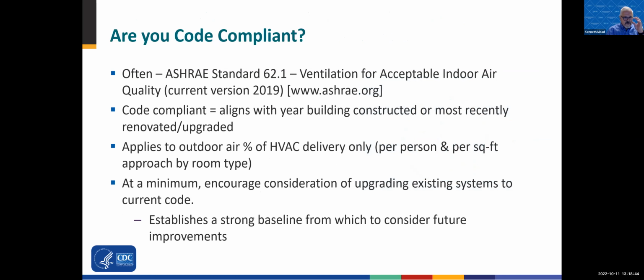One of the first things that we've tried to emphasize throughout the pandemic is, are you code compliant? If we step outside of those prescriptive areas within healthcare where we have protective airflow paradigms because we have known infectious aerosol generators in them, then that often takes us into the area of ASHRAE Standard 62.1, ventilation for acceptable indoor air quality. Code compliant, as we refer to it, aligns with the year the building was constructed or most recently renovated or upgraded. It applies to the outdoor air percentage of the HVAC delivery only, so it's not the total airflow.